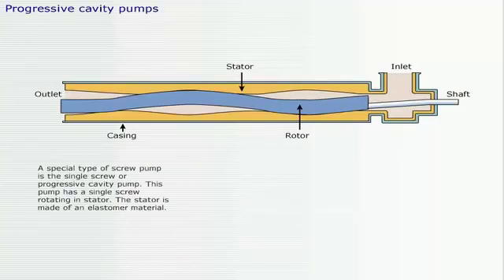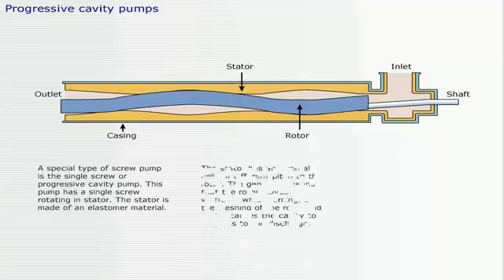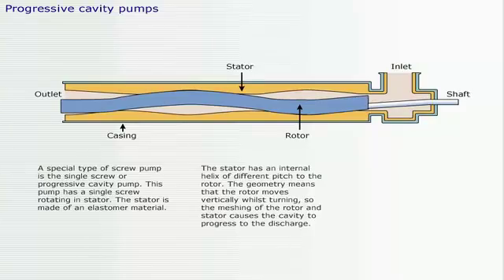A special type of screw pump is the single screw, or progressive cavity pump. This pump has a single screw rotating in stator. The stator is made of an elastomer material. The stator has an internal helix of different pitch to the rotor. The geometry means that the rotor moves vertically whilst turning, so the meshing of the rotor and stator causes the cavity to progress to the discharge.